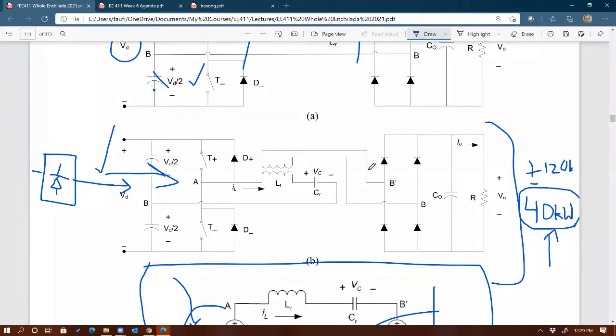And keep in mind that this power supply is also being used for a CT scanner, right? So you want this DC to DC converter to be clean from noise, especially audible noise, right? Because you're going to put a patient inside the CT scanner, and you definitely don't want to annoy the patient with some audible noise from the power supply. So noise is a very important thing.